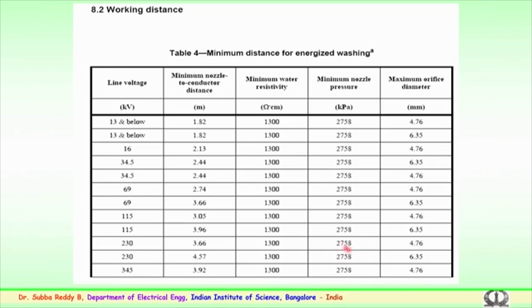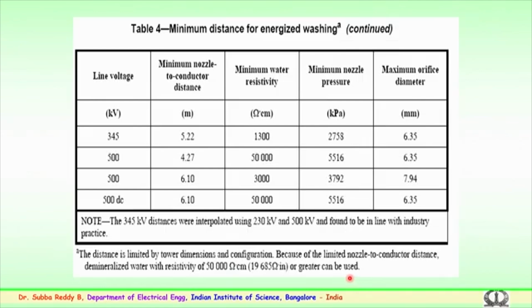As the voltage level increases, a similar pattern is being observed for further 400 or 765 kV transmission systems. Similar distance have to be maintained, which are also given in the standards. So, working distance is very important, care has to be taken, safety is of utmost importance in the cleaning of the insulation. The table 4 here shown gives the minimum distance again for the energized conditions.